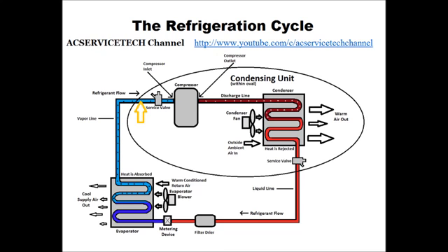If you took it from right in the middle of the evaporator coil, right after the saturated state where it turns into a complete vapor, the temperature increase from there all the way over to the service valve next to the compressor is called the total superheat. After that it just enters back into the compressor as a low pressure, low temperature vapor refrigerant, and the refrigerant cycle starts all over again.